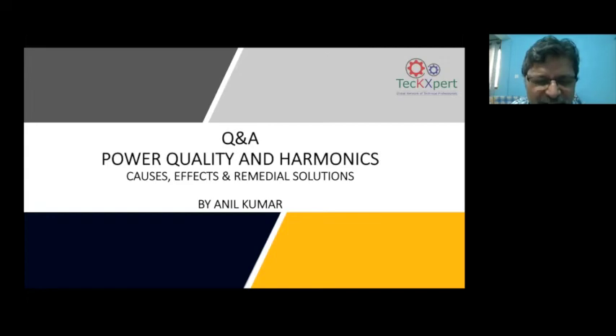There are active harmonic filters, but some manufacturers I know want to put only selective filtering, because the moment it goes to broadband filtering, the active harmonic filter efficiency comes down. Number two, the derating issue comes up. It should be properly derated, but everywhere we economize the cost, so we don't derate. And the third thing is that an active harmonic filter produces higher frequency harmonic currents. These need not be within the harmonic range. They can be at 9 kilohertz, 10 kilohertz, and those produce electromagnetic interference as noise. Then through the ground, your electronics can fail. So the right active harmonic filter is very important. Otherwise, all these cumulative problems can come.